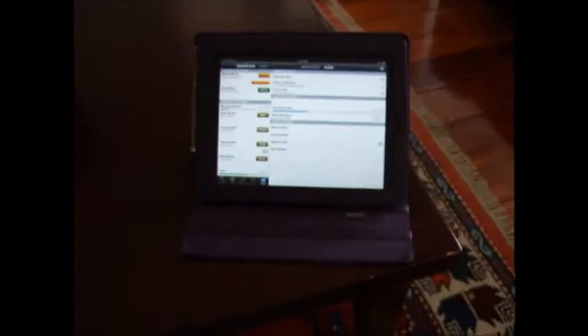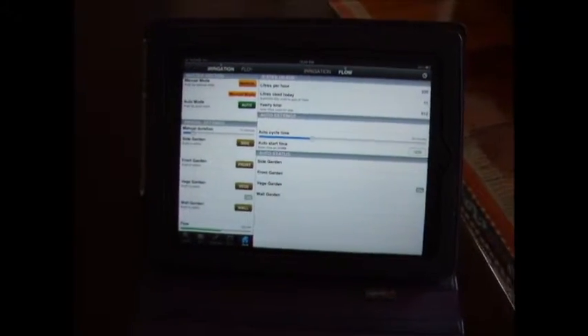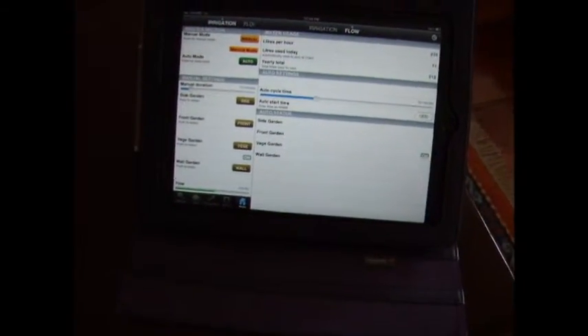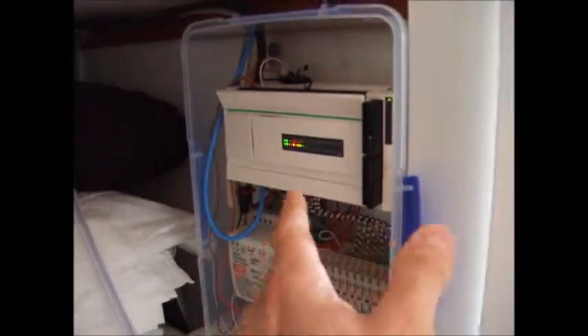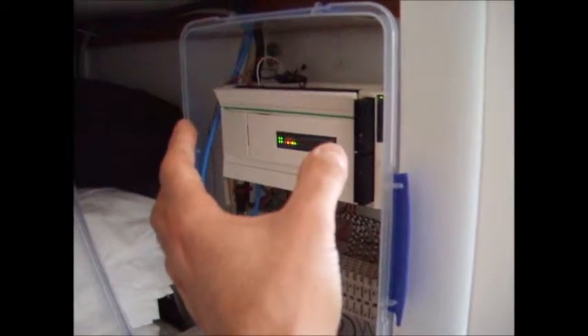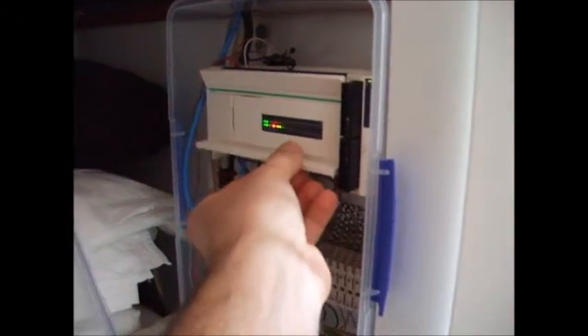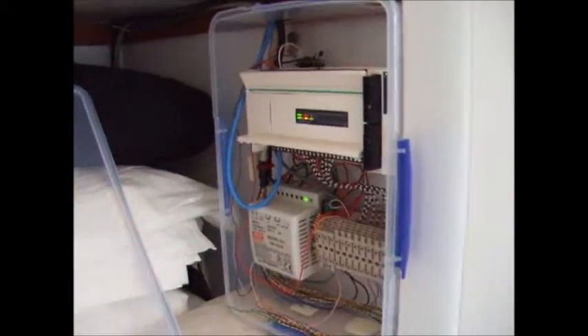So basically these 3 devices are able to communicate together by using a standard protocol. In this case it's Modbus, and we're doing it over the Ethernet and over the internet. Note, there are several features that are needed in order to make a system like this happen. First of all, you have to have an Ethernet adapter or built-in Ethernet in the PLC. It doesn't come standard with every PLC, especially in the compact types.